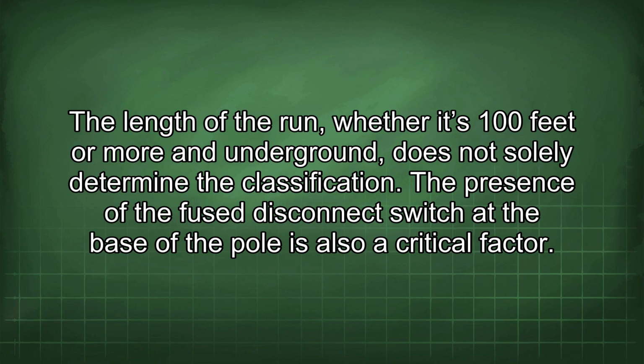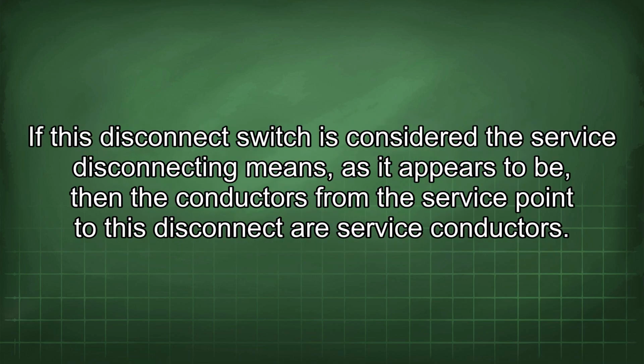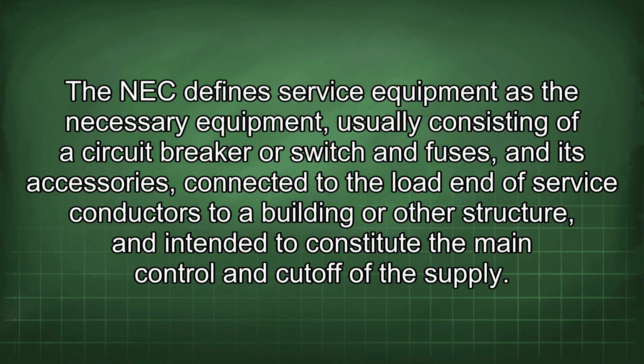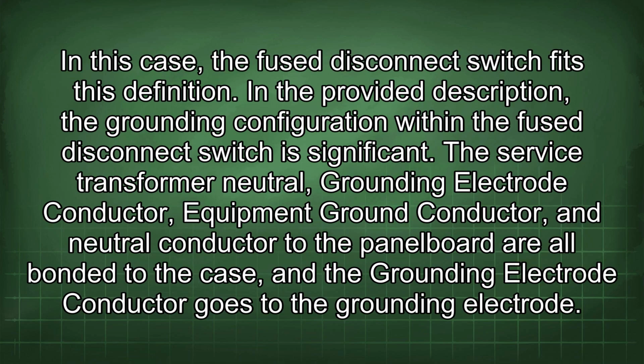The length of the run, whether it's 100 feet or more and underground, does not solely determine the classification. The presence of the fuse disconnect switch at the base of the pole is also a critical factor. If this disconnect switch is considered the service disconnecting means, as it appears to be, then the conductors from the service point to this disconnect are service conductors. The NEC defines service equipment as the necessary equipment, usually consisting of a circuit breaker or switch and fuses, and its accessories, connected to the load end of service conductors to a building or other structure, and intended to constitute the main control and cutoff of the supply. In this case, the fuse disconnect switch fits this definition.